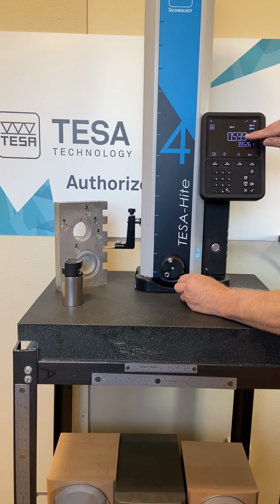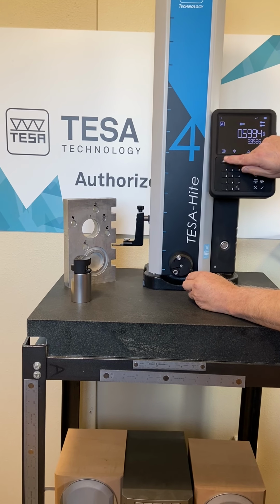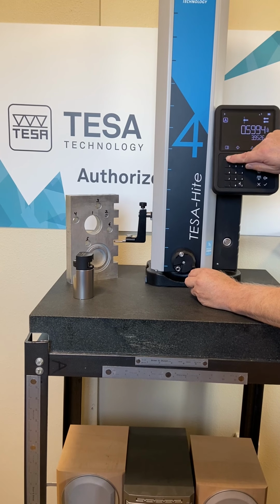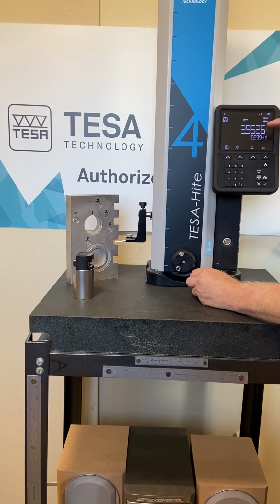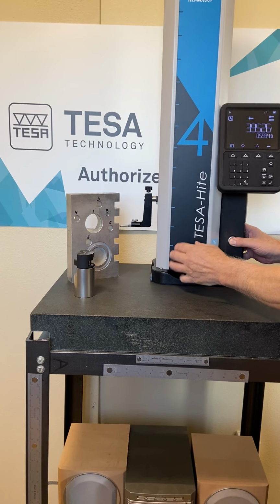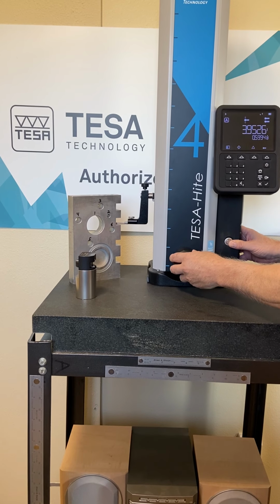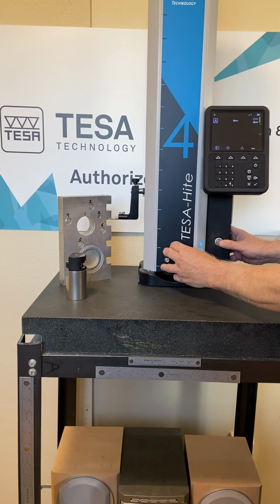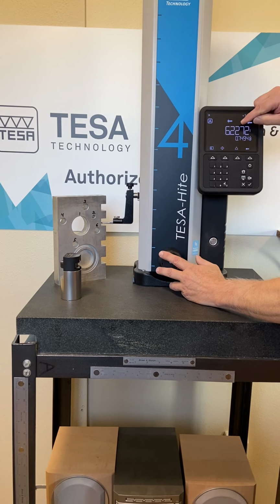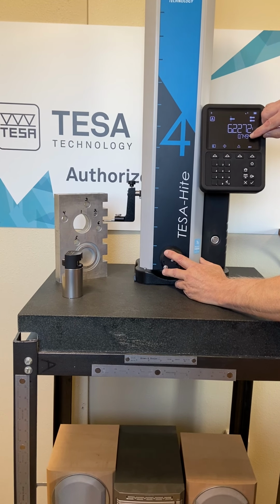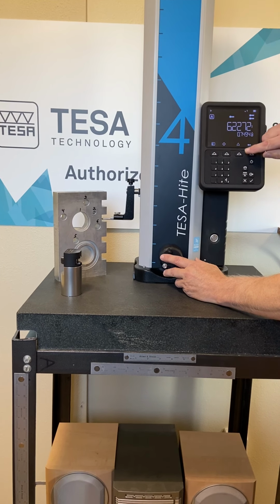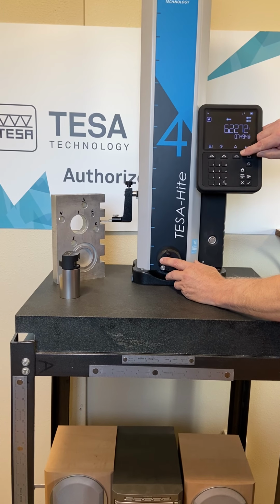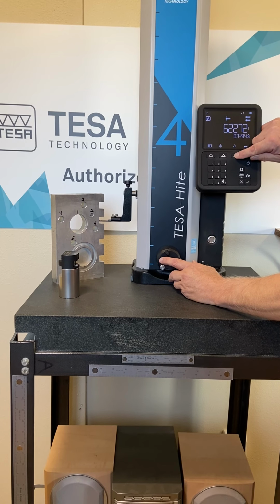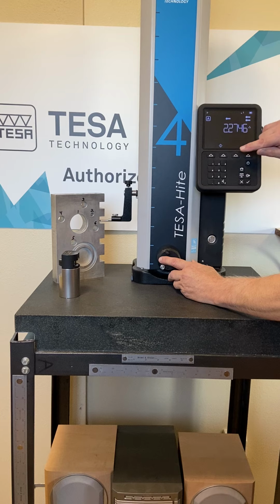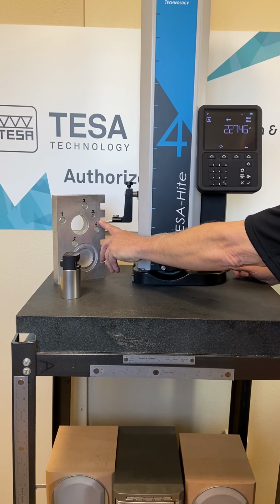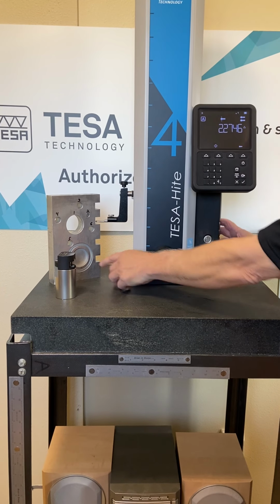If I want to invert those numbers and see them just the opposite way, my inversion symbol is right there. I hit that function key, and now I'm seeing it just the opposite. If I come up here, take a bottom hit, take a top hit. So now my center line measurement's up on top, my thickness is on the bottom. Delta key right there, if I hit that, that's going to give me my difference between my last 2 measurements, which happen to be center line from there to center line from there.